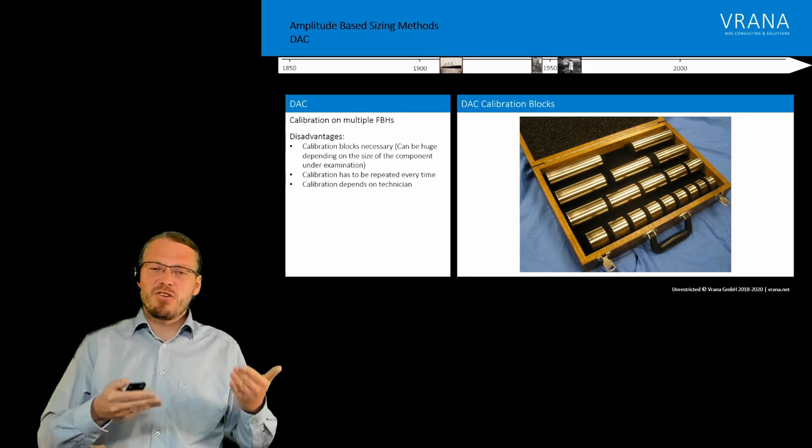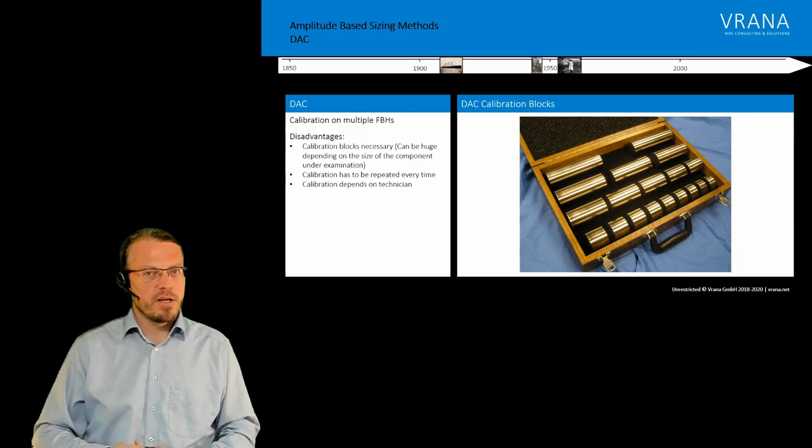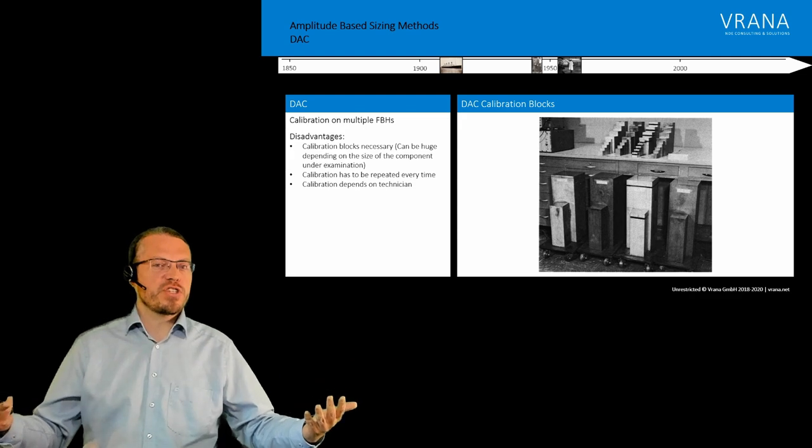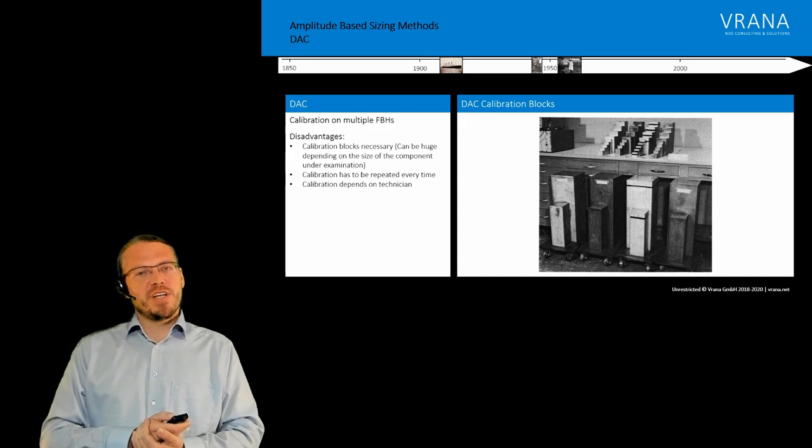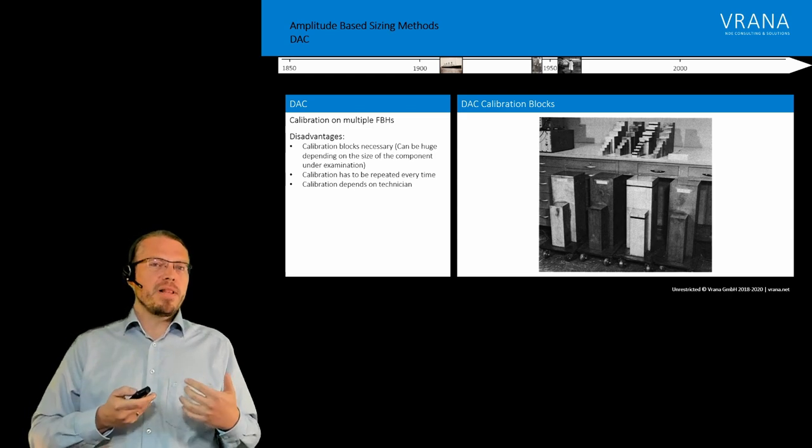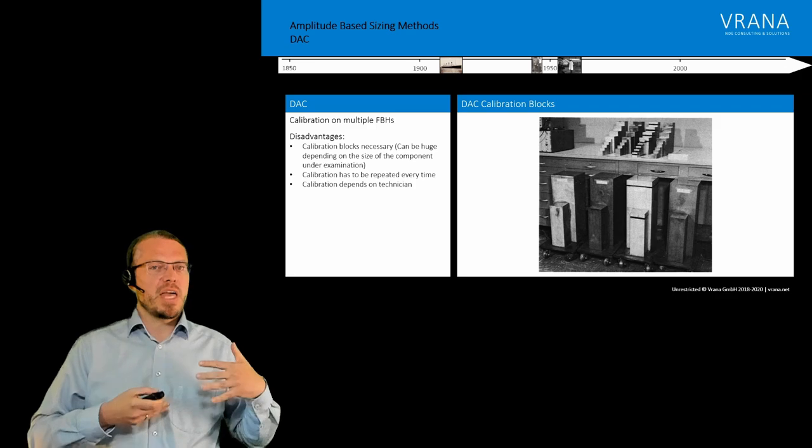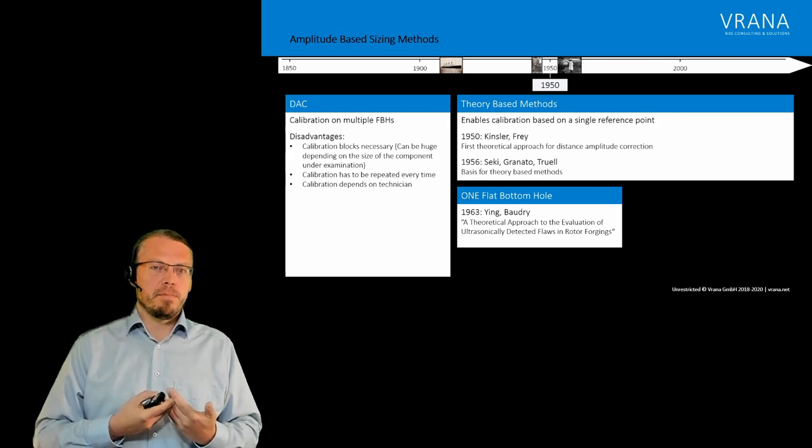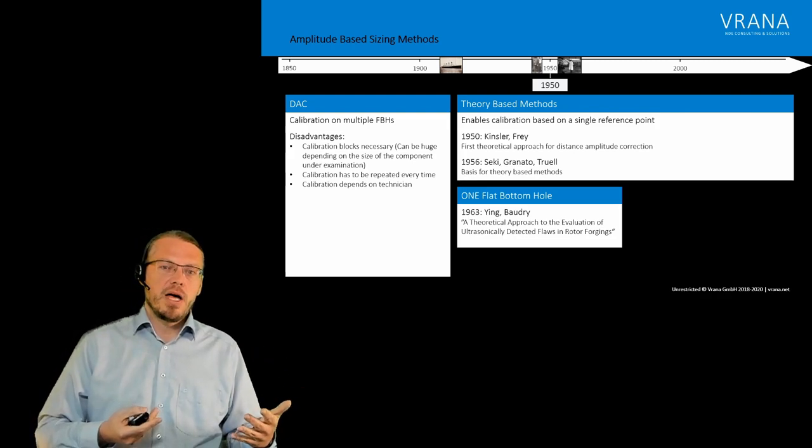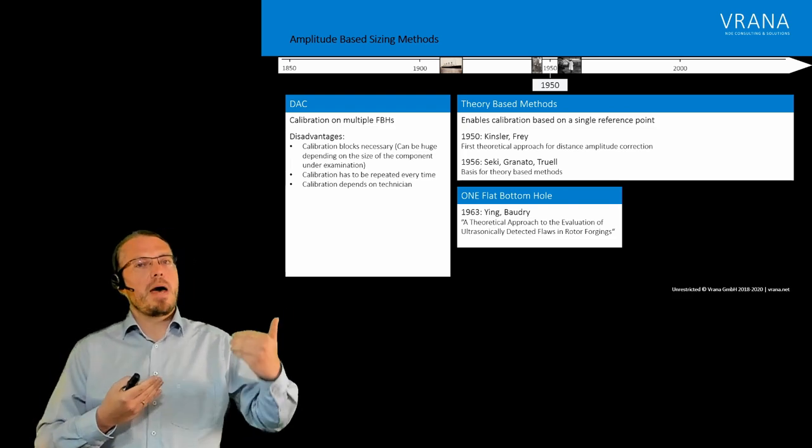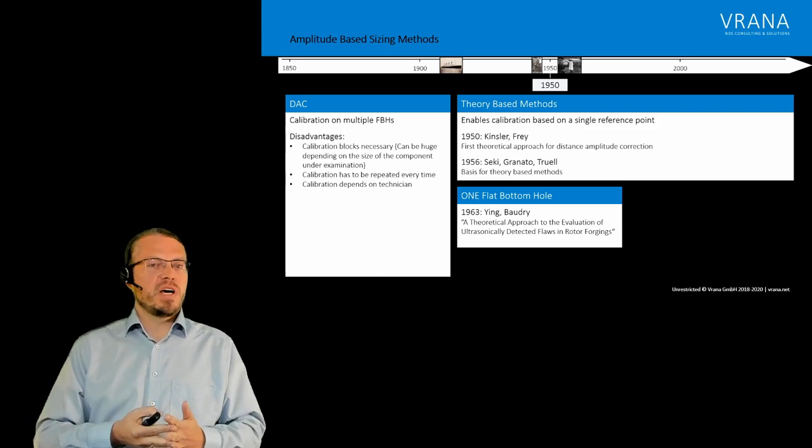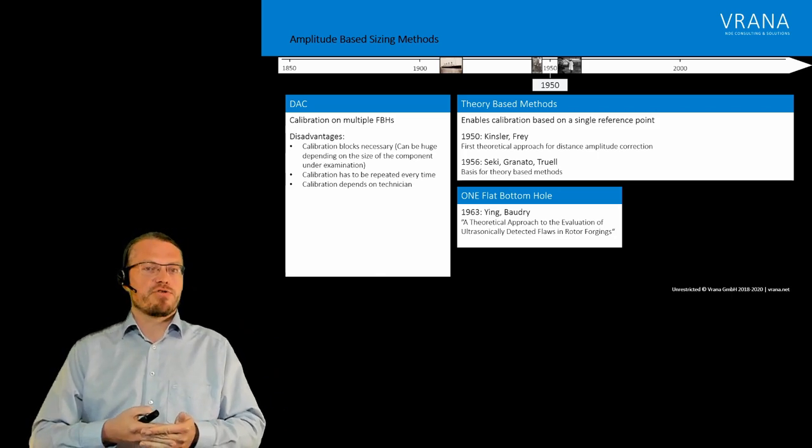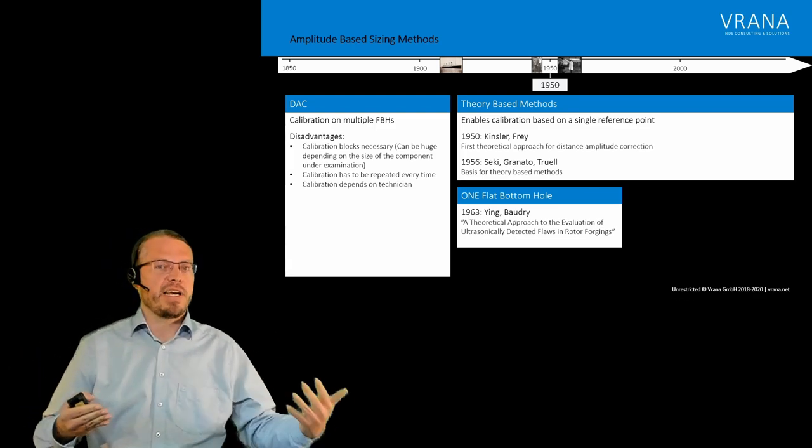Now to get really decent numbers from those blocks, that's a lot of work. And if we think about big components like large forgings, we're getting in those sizes of calibration blocks. And they are not anymore really that handy. So people already from the very beginning of ultrasonics thought about okay, how can we make our lives a little bit simpler. And there were some early books from around 1950, one from Kinsler and Frey. And they really worked on the first theoretical approach for a so-called distance amplitude correction. And the book from 1956 from Seki, Granato, and Truell, that is really more or less the basis for all those theory-based methods which followed later on. For example, that one from Ying and Baudry, which actually used one, a single flat bottom hole for all the calibration, and all the other stuff they do with a lot of math.